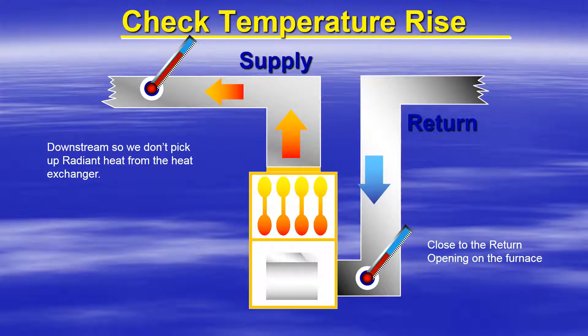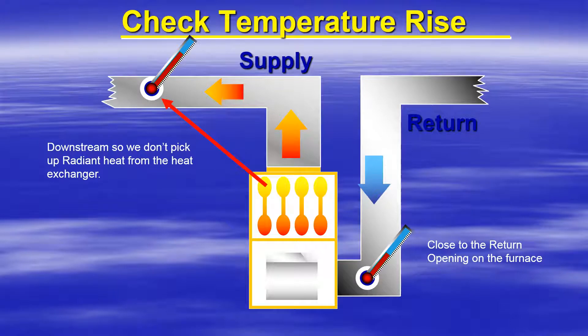To take the temperature rise on a gas furnace, you want to take the return air temperature close to the return opening on the furnace. You then want to take the supply air temperature downstream of the furnace, so you don't pick up radiant heat from the heat exchanger.